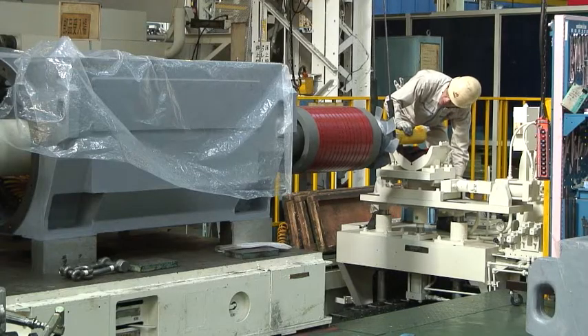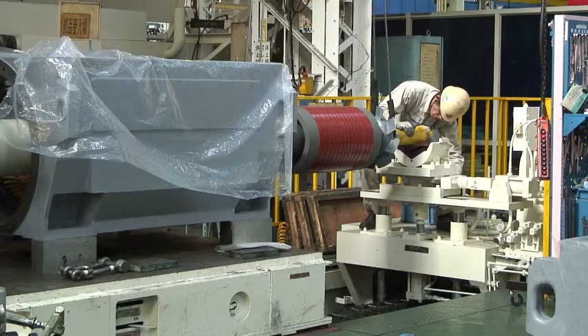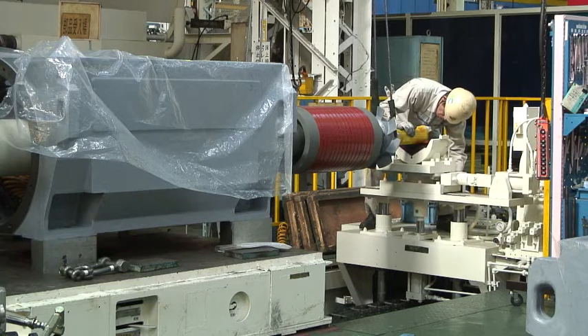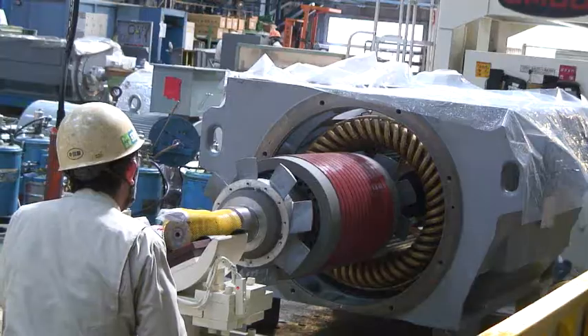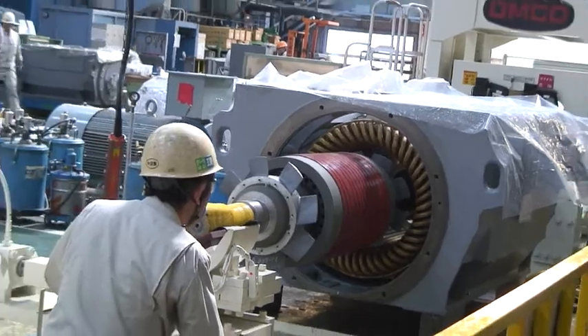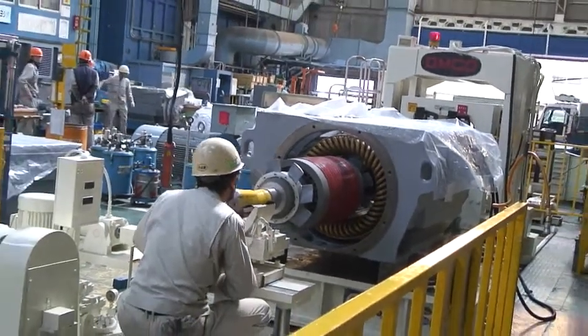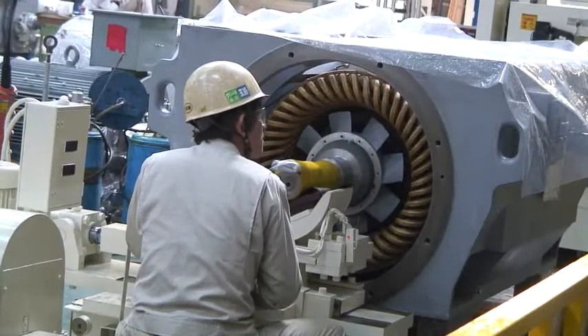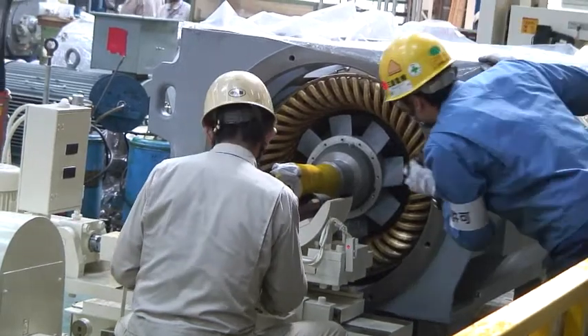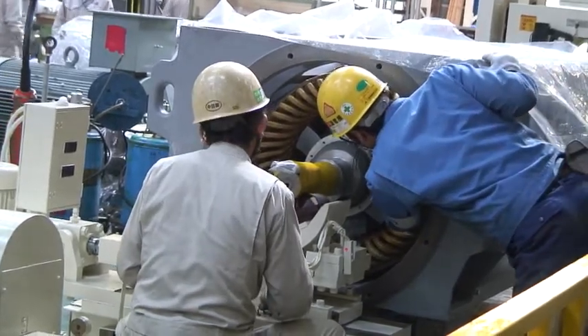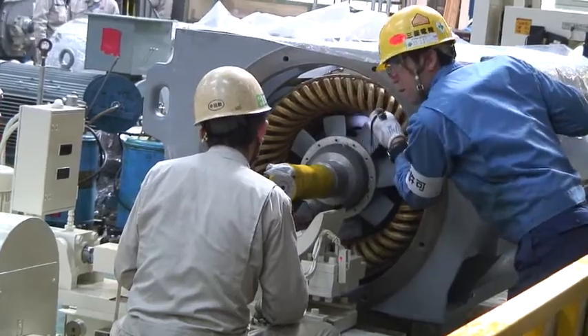Care must be taken when inserting the rotor into the stator, in contrast to traditional methods requiring 2 overhead cranes and 4 to 5 operators for this task. This machine in the Nagasaki plant automatically aligns the rotor inside the stator during assembly. As a result, only 2 operators are required to control the process.